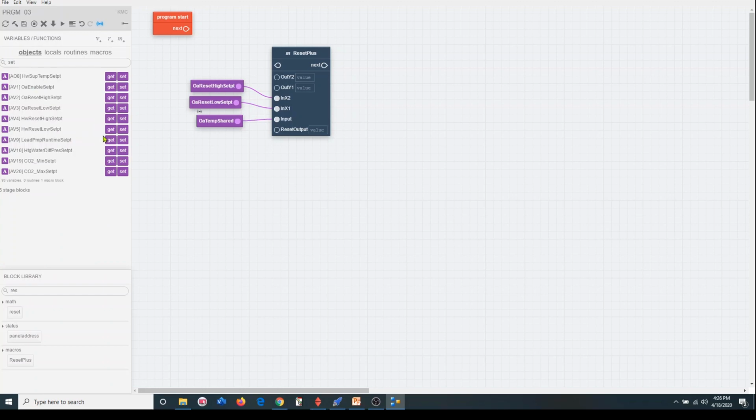Okay, so here's the high and the low. So X1, what do we want Y1 to be at X1? We want that to be the high value. So we're going to take the high there and attach that to there. And then the low, of course, you're going to put up there. And then attach this. Now the way I programmed this is it's ambidextrous. It doesn't matter how you did it. If you put the water temperature low above the water temperature high, and then you would switch the other two, it will automatically calculate it regardless of what direction you're going.